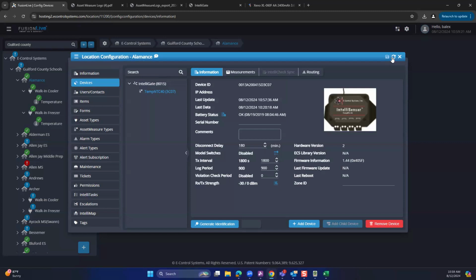When we put the new batteries in, a little LED light will come on inside the sensor, letting you know that you have good battery voltage inside the unit. You simply have to trigger our sensor with our magnet tool to take a real-time temperature and pair that newly changed battery device to the system. So if any of the IntelliSensor devices go down and have low batteries, we generally just have to change those batteries. We can trigger the device by sliding the magnet tool down the right side of it, across the white ID label on the outside of the right side of the device.